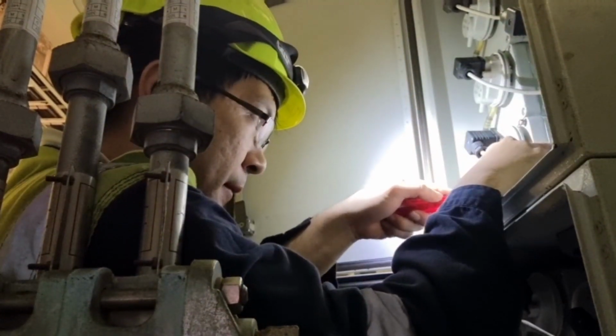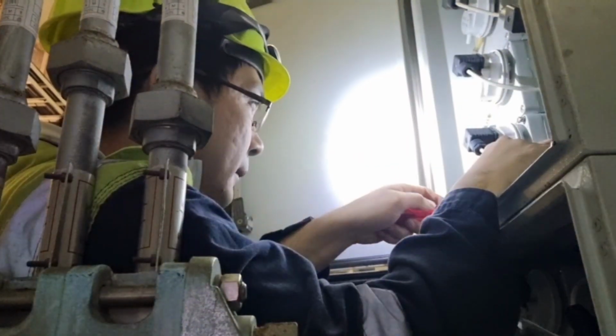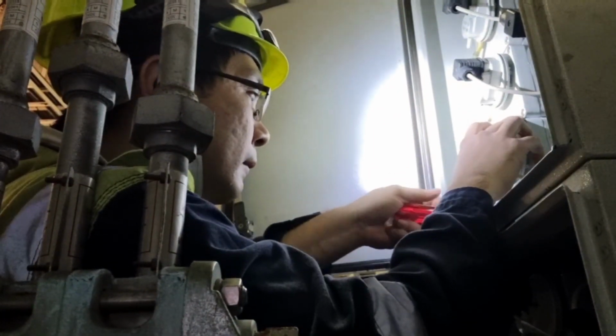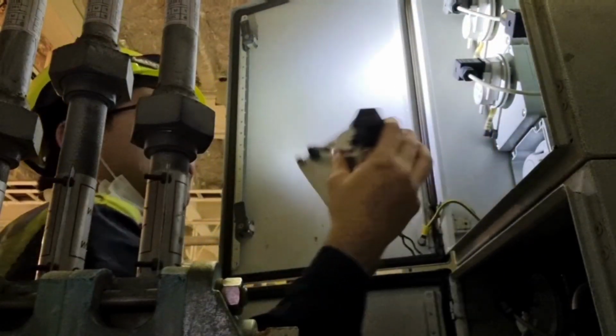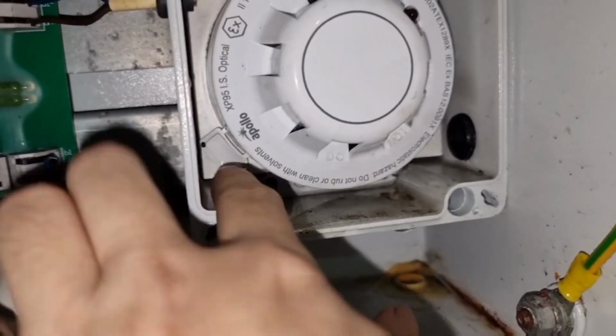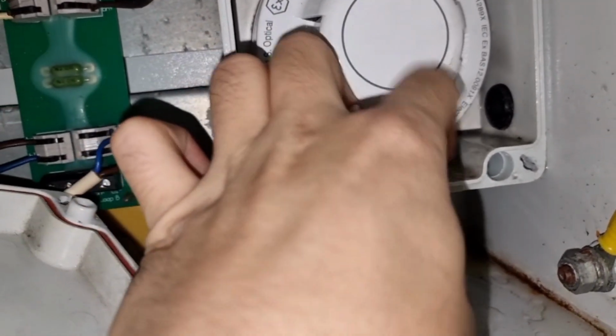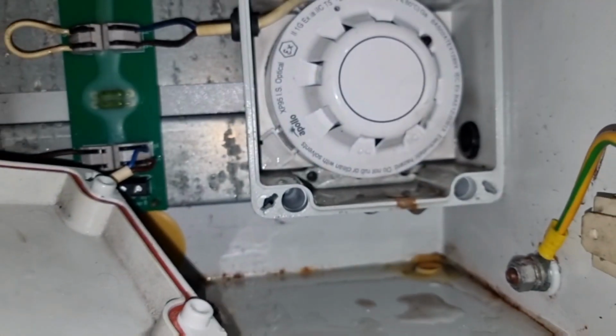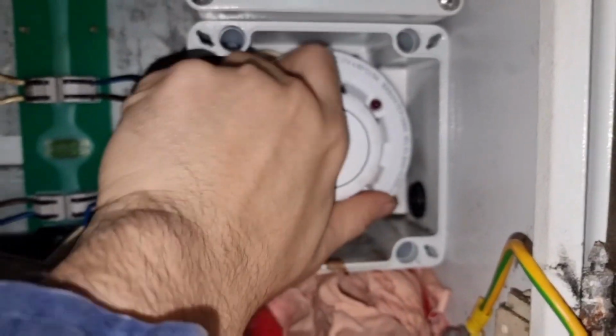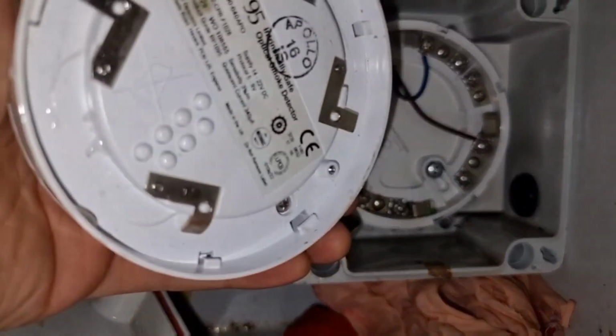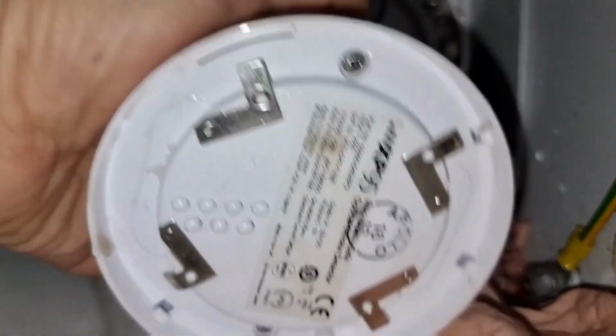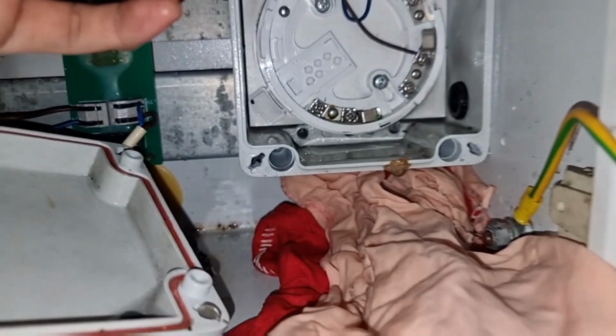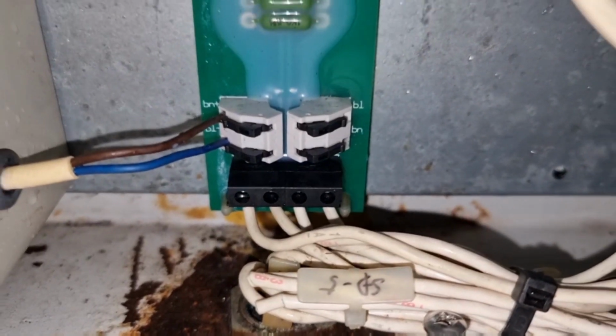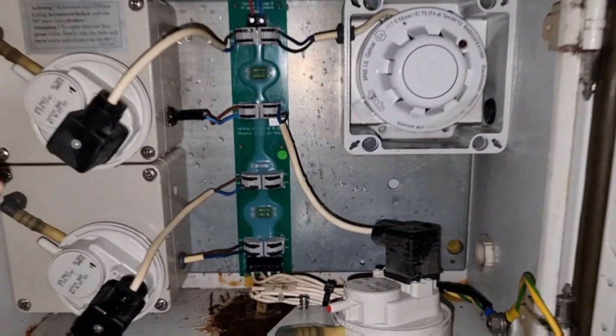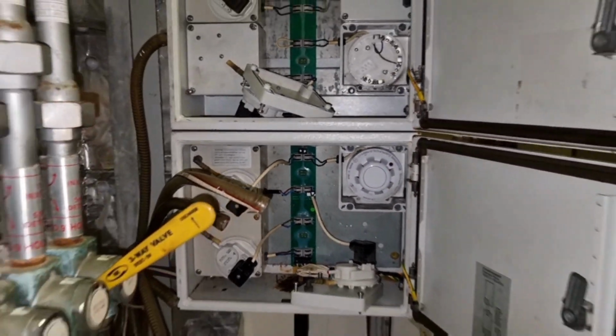So we called the fitter to rectify this one, while I proceeded again to the CO2 room to dismantle all the sensors, the PCBs, and all the wirings on the inside. This also includes the smoke detectors, the airflow sensor, and all other components which were affected by this situation. So my plan is to use contact cleaner in cleaning all these contacts and all the components so that we can ensure that everything will be just fine. I hope that everything will be okay after that.